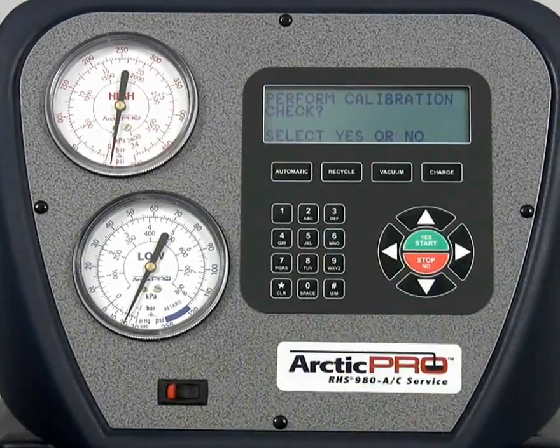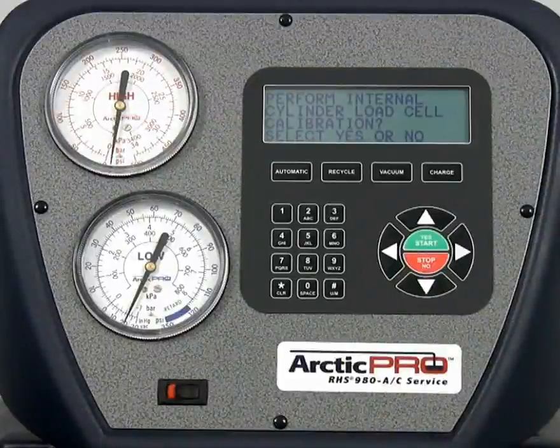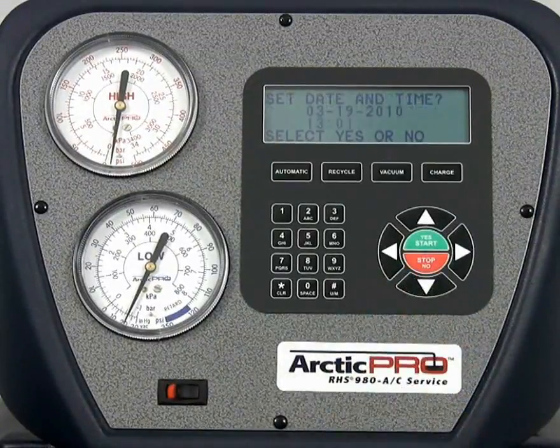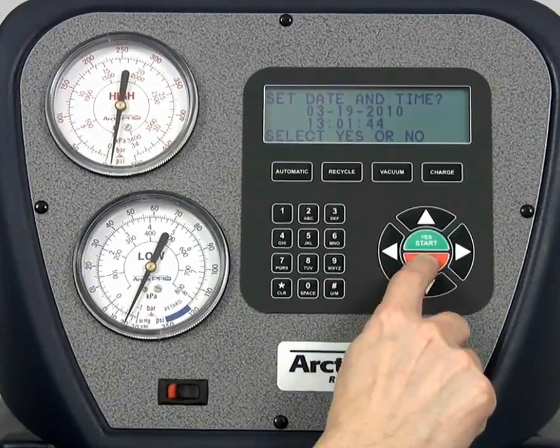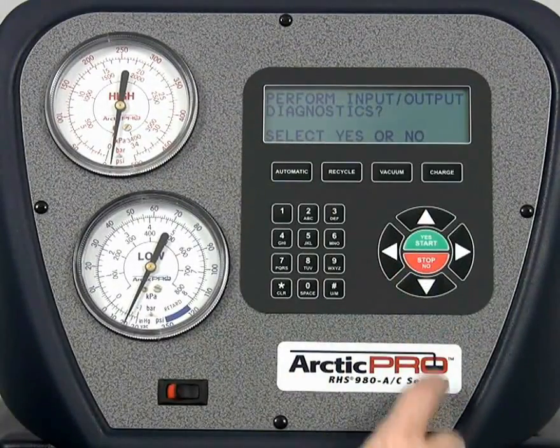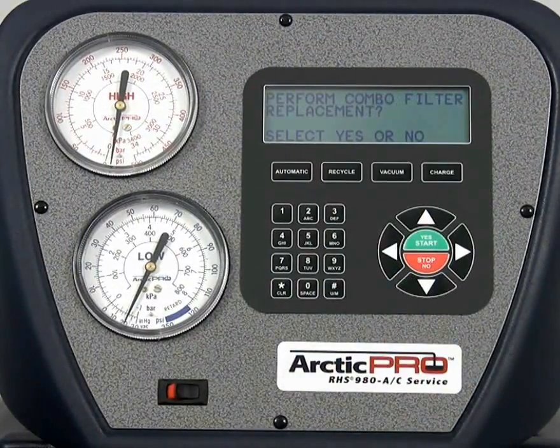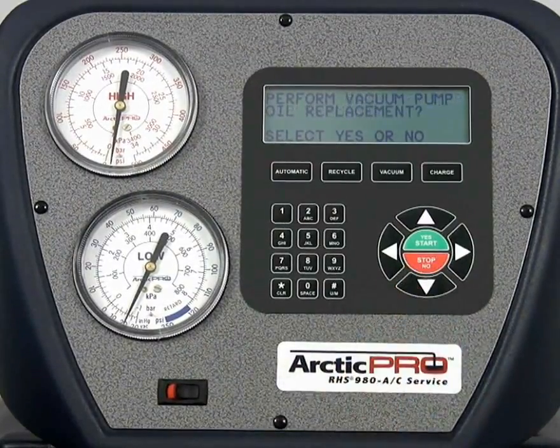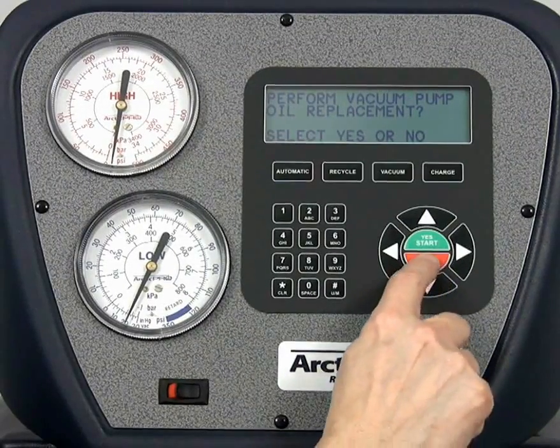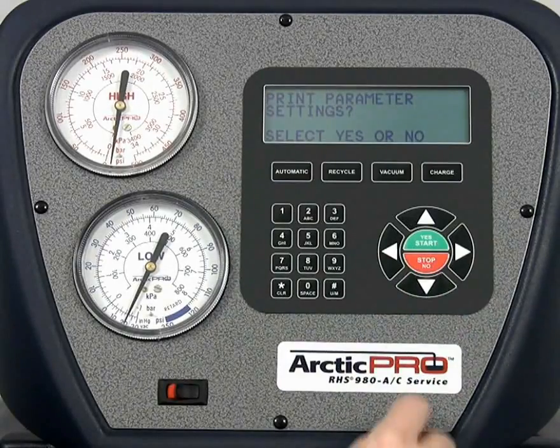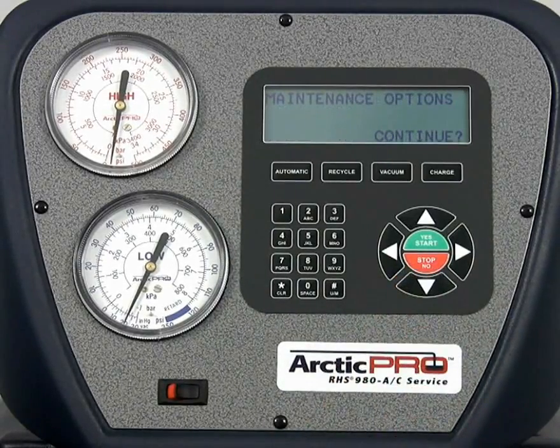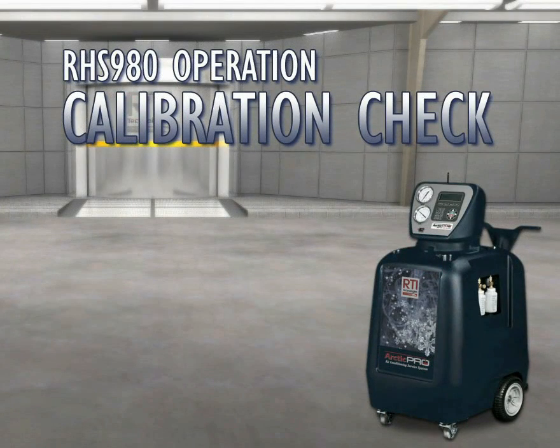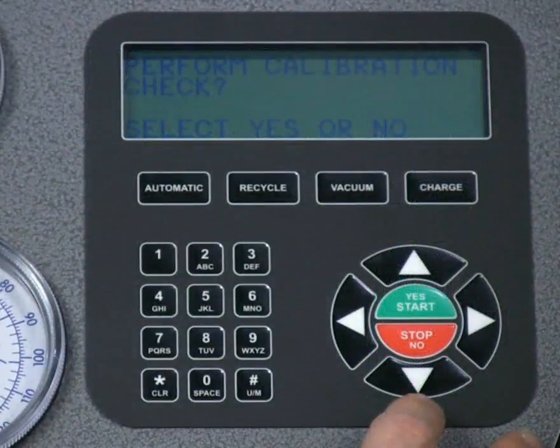The following functions can be accessed in Maintenance Options: Calibration check, Load cell calibration, Vacuum sensor calibration, Set date and time, Input and output diagnostics, Combo filter replacement, Vacuum pump oil replacement, Print parameter settings. Now we'll cover in detail all of the most commonly utilized functions in Maintenance Options. Let's do a calibration check. Again, as a reminder, a calibration check is not a load cell machine calibration.